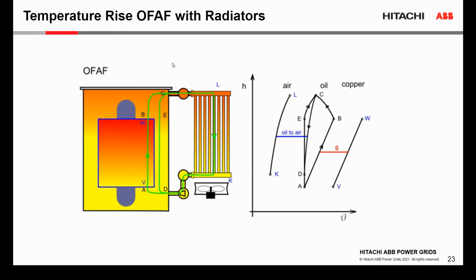We can combine radiators, fans, and pumps together. So by adding the pumps to the circuit, we change the oil circulation. We force oil into the tank, and at the same time we change the temperature of oil. And by changing the top oil temperature, we can affect the temperature of the hotspot. We can reduce the temperature of the hotspot, and we can also reduce the size of the cooling system. And at the same time, we can have a transformer loaded to most likely 60% of the rated capacity without fans and pumps running. But with this solution, we add one more device, which is the pump.